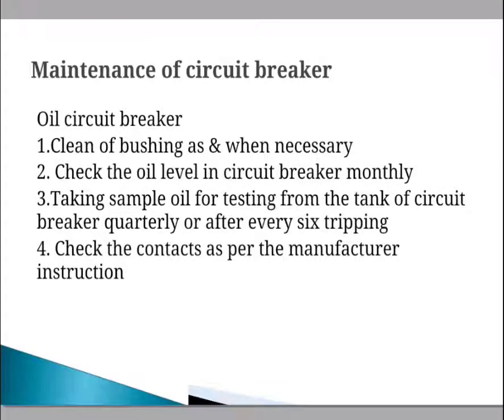For maintenance of the oil circuit breaker, we have to check the bushing — if dust has accumulated, clean it whenever needed. Check the oil level monthly; if low, add oil or investigate why the level is low. Take a sample of oil for testing from the tank quarterly or after every six trippings, and check the dielectric strength. Check the contacts as per manufacturer instructions.